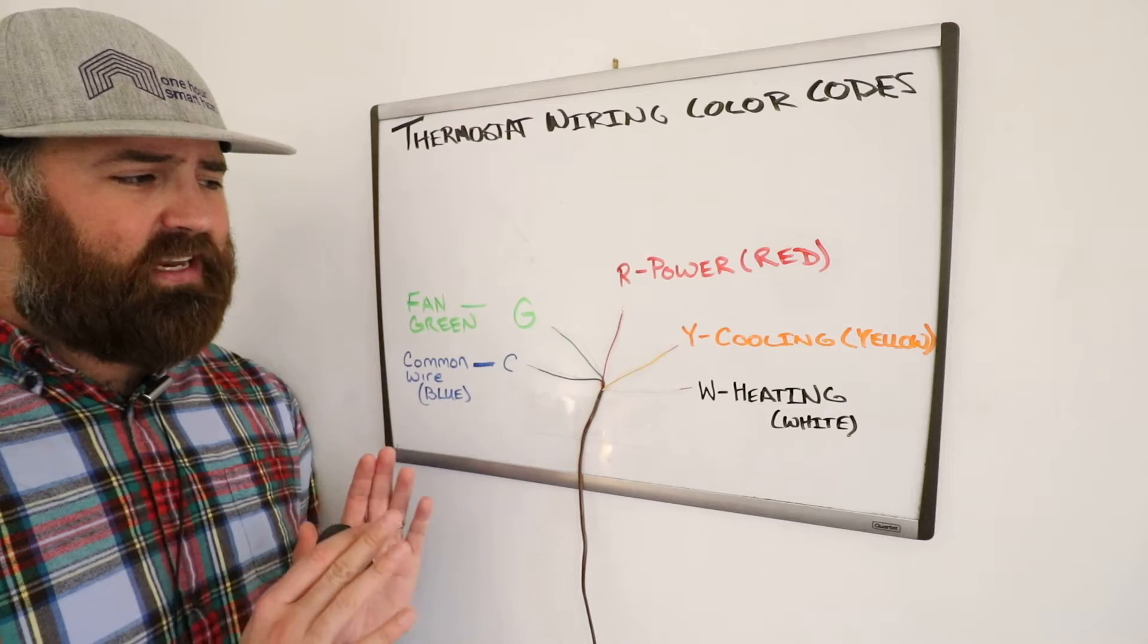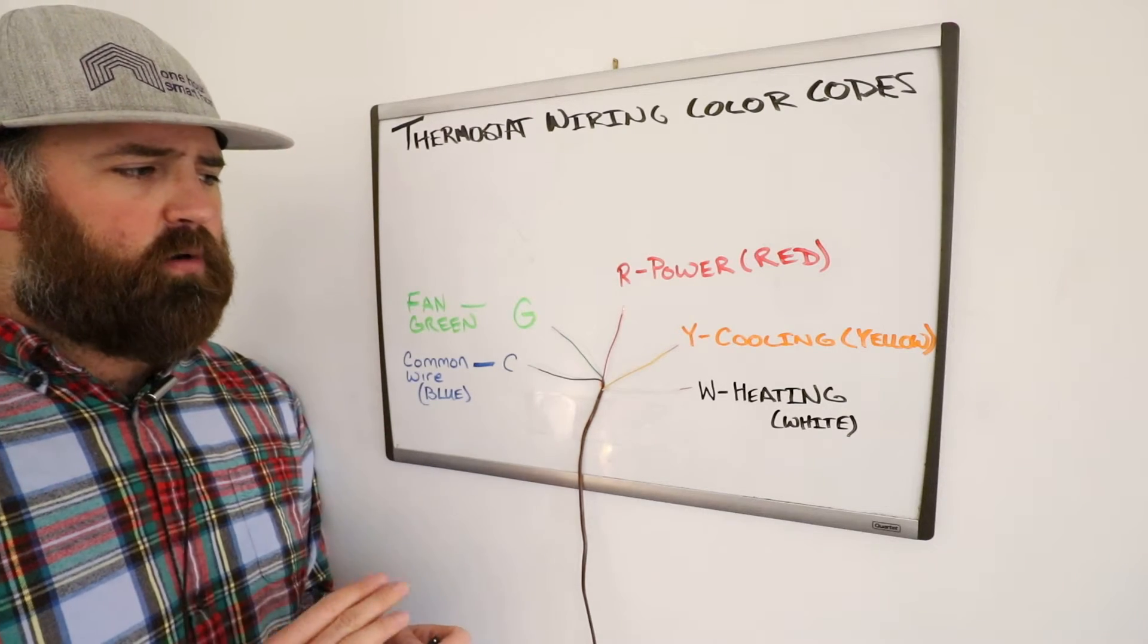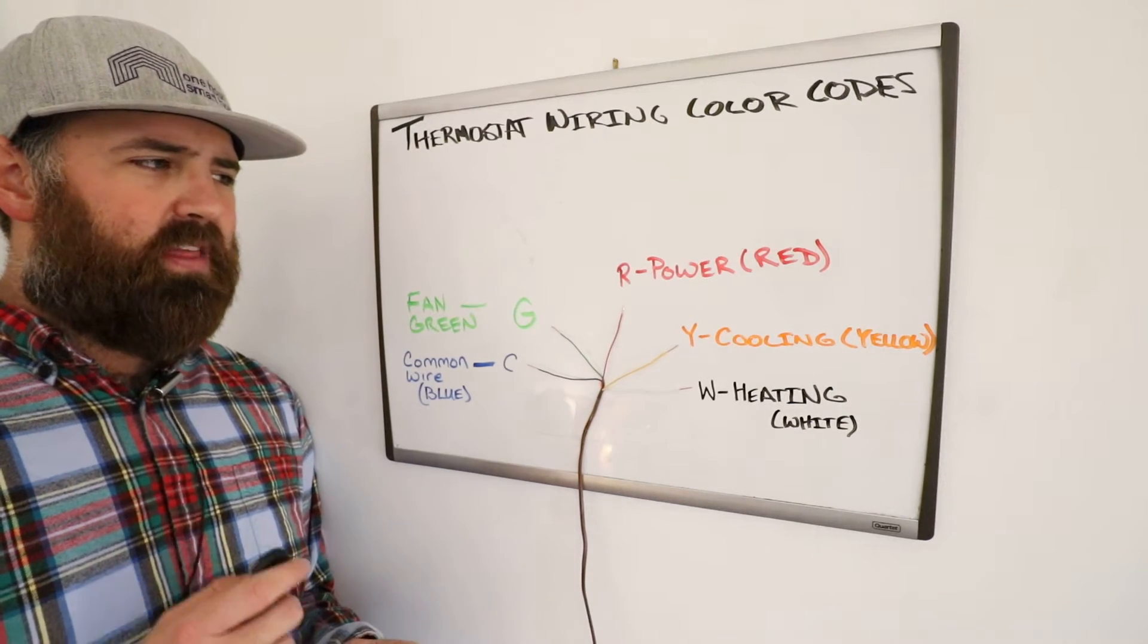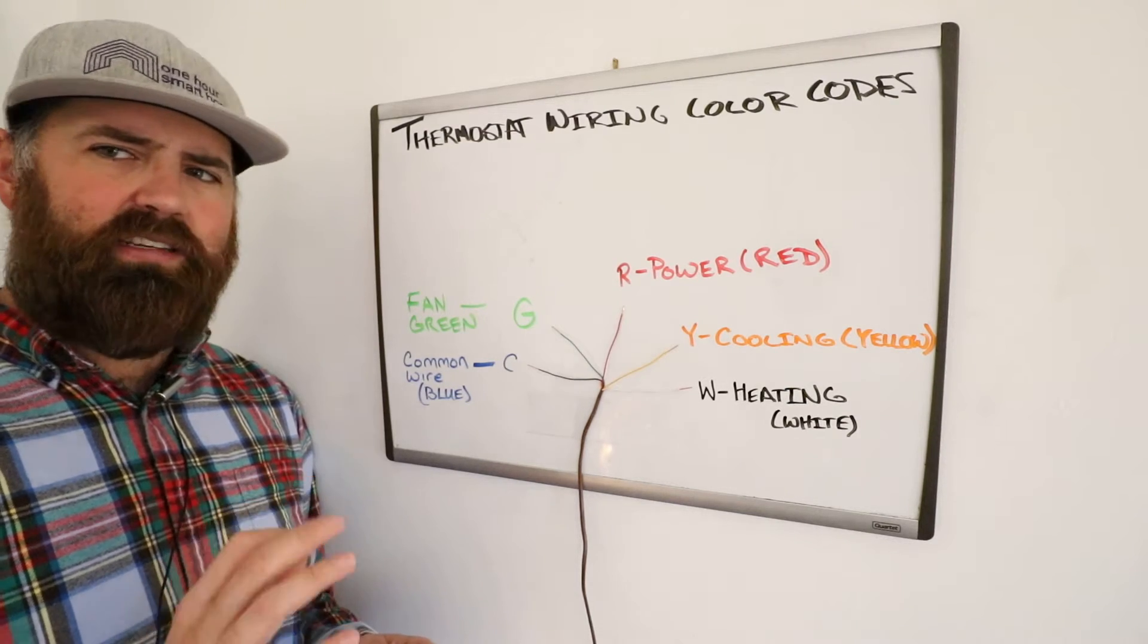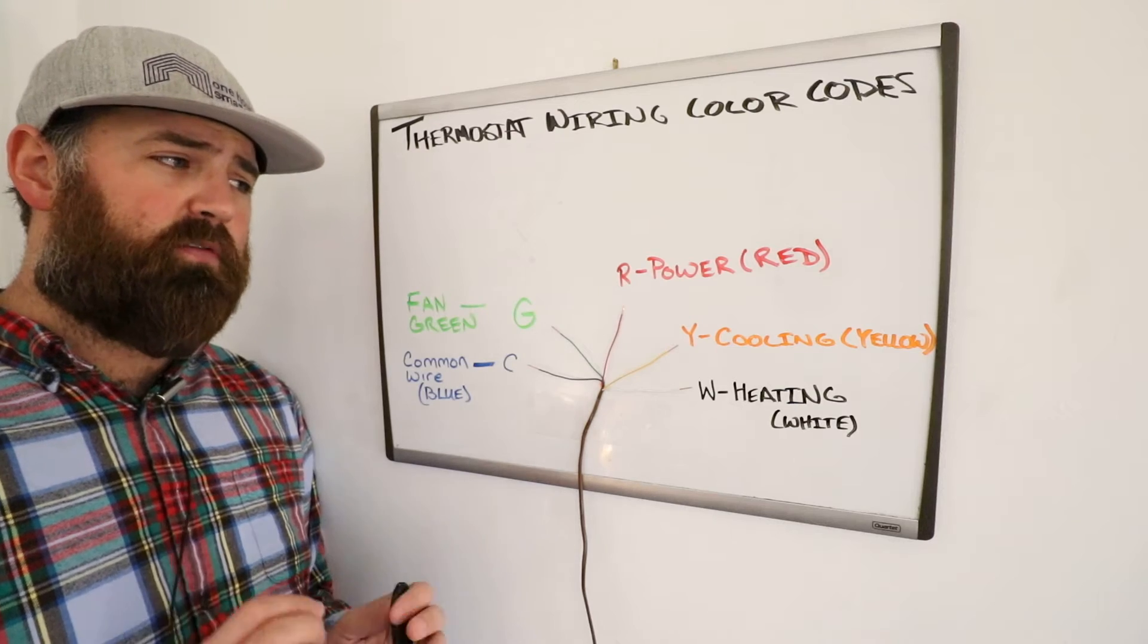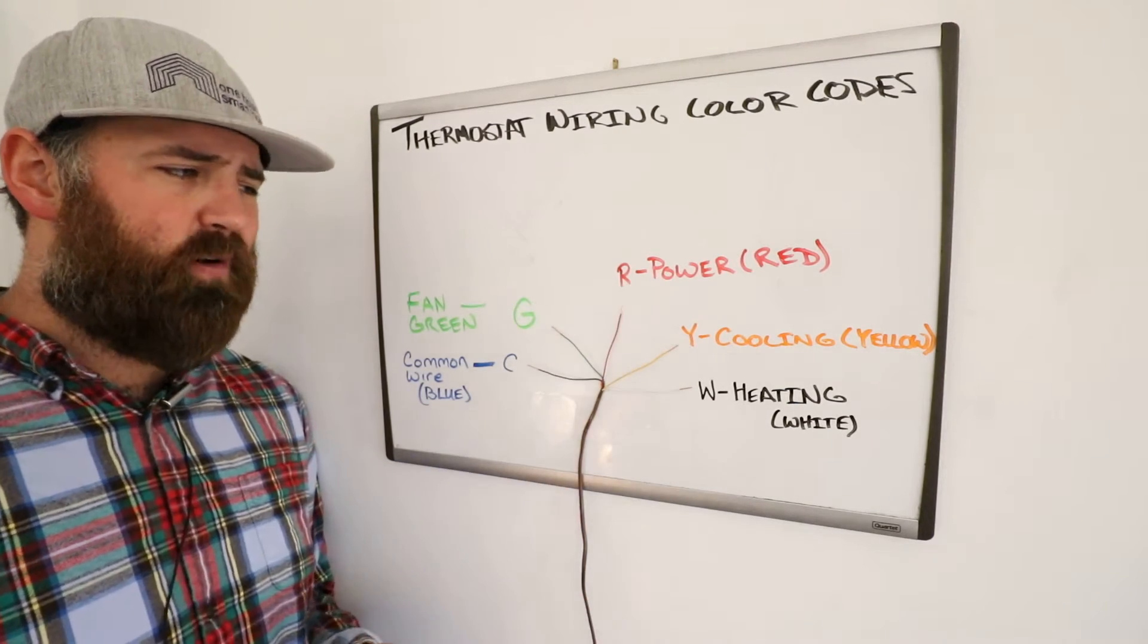So that is why we did this video, and the R-wire, which is right here in the center, is probably the most important wire. That is the power wire. So from your furnace, you're getting anywhere between 18 and 24 volts depending on your system. It should be 24 for most systems, but that's coming through the red wire or the power wire.